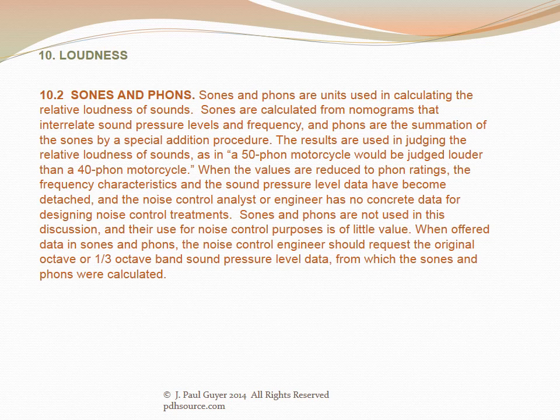Sones and phons are units used in calculating the relative loudness of sounds. Sones are calculated from nomographs interrelating sound pressure levels and frequency; phons are the summation of sones using a special addition procedure. However, when values are reduced to phon ratings, the frequency characteristics and sound pressure level data are detached, leaving no concrete data for designing noise control treatments. Sones and phons are not used in this discussion; when offered such data, the noise control engineer should request the original octave or one-third octave band SPL data.